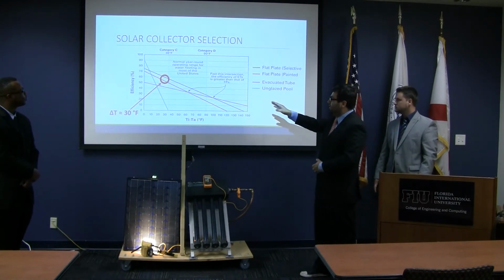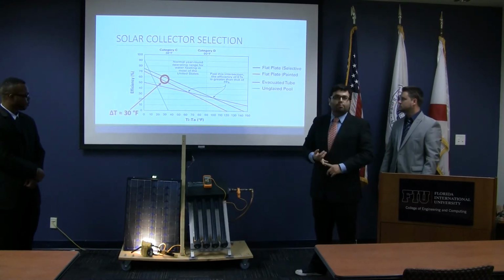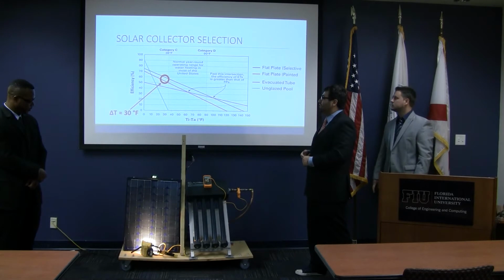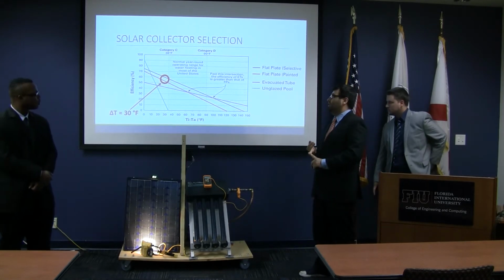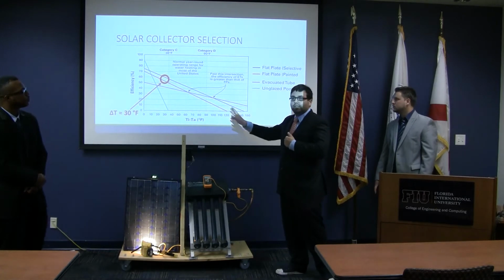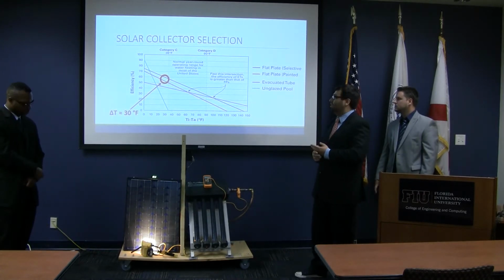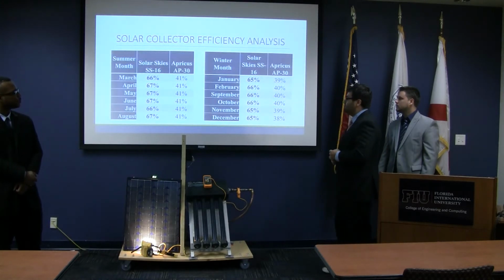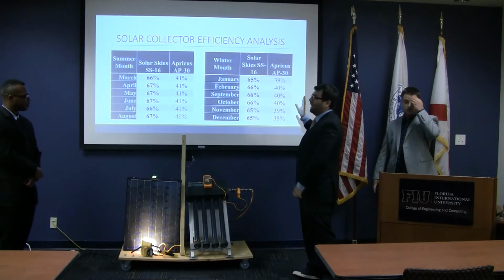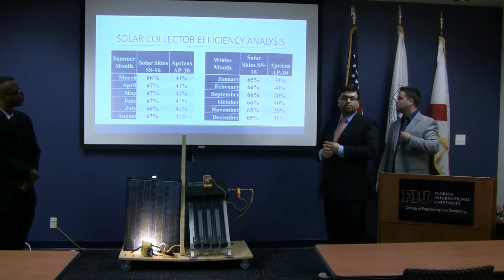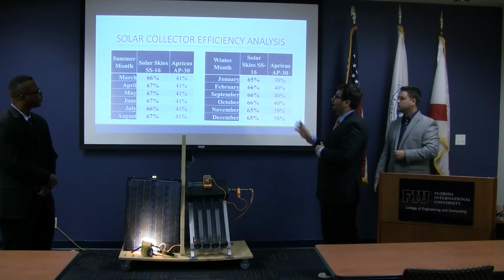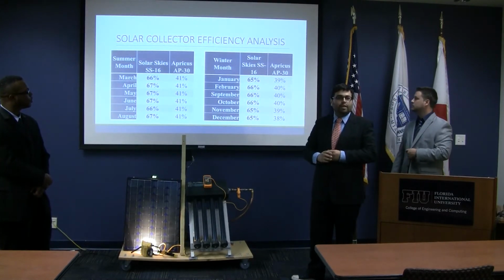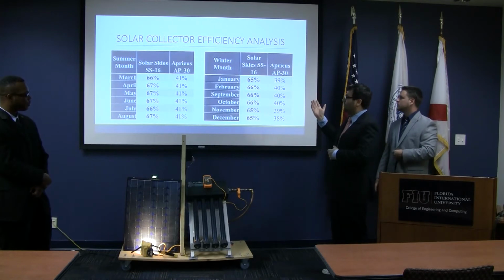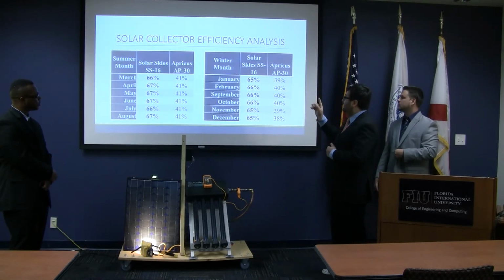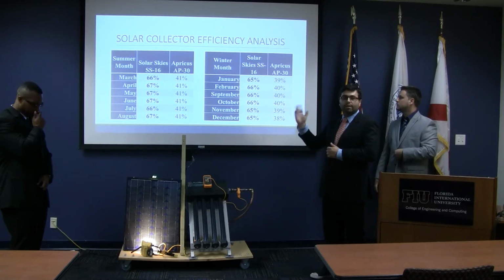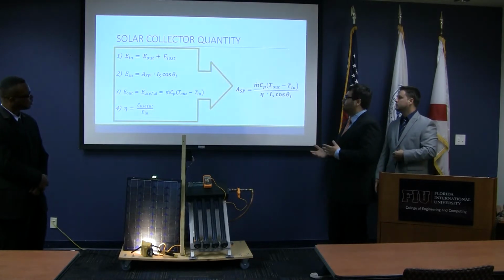So basically, what we see here is the different technologies. We have evacuated tubes, we have flat plate solar collectors, and we ended up choosing the glazed flat plate collectors, because for delta T, it was the best. We could get the best efficiency. If you look at these 2 tables, we compare 2 different technologies. We compare evacuated tubes in this size using the equations of the Solar Rating Certification Corporation. And on the left side, we look at the flat plate collectors. And we can see here, same as we saw on the graph, that the flat plate collectors have a better efficiency for the conditions that are present in our project.